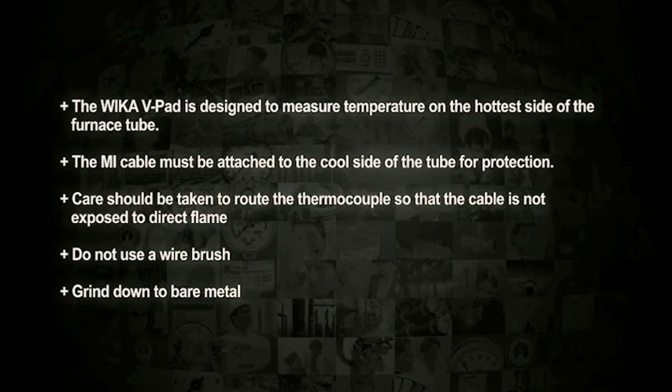The WIKA V-Pad is designed to measure temperature on the hottest side of the furnace tube. The MI cable must be attached to the cool side of the tube for protection. Care should be taken to route the thermocouple so that the cable is not exposed to direct flame.